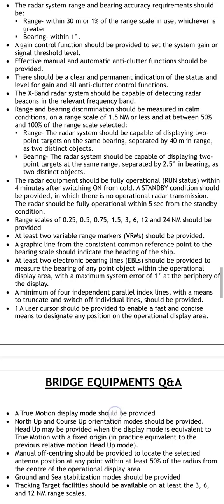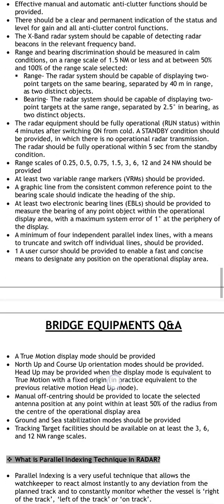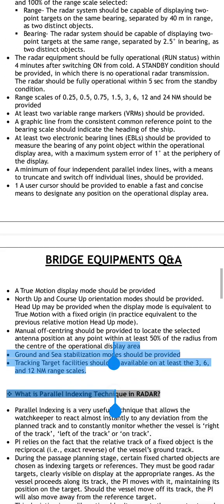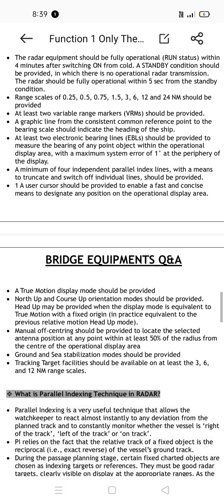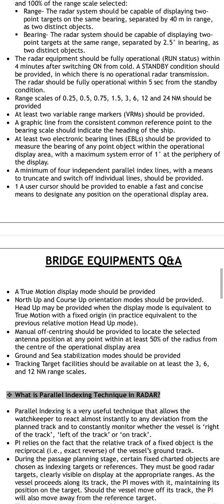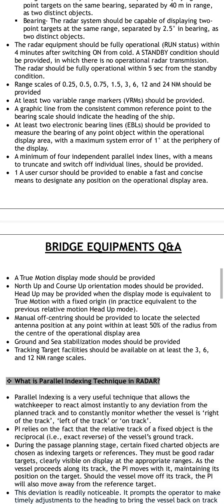The radar system should be capable of displaying two targets on the same bearing separated by 40 meters as two distinct echoes, and two targets separated in bearing by 2.5 degrees as two distinct echoes. The radar equipment should be fully operational within 4 minutes after switching on from cold. A standby condition should be provided in which there is no radar transmission. The radar should be fully operational within 5 seconds from the standby condition.